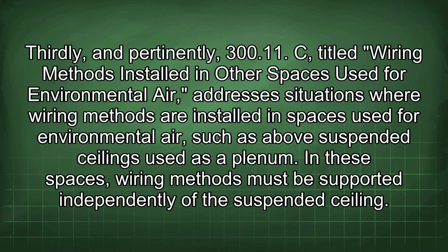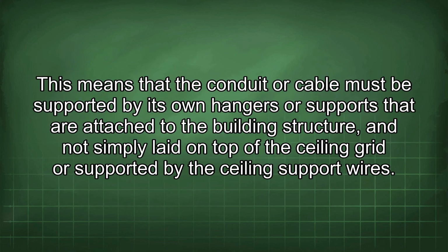Thirdly, and pertinently, 300.11 C, titled Wiring Methods Installed in Other Spaces Used for Environmental Air, addresses situations where wiring methods are installed in spaces used for environmental air, such as above suspended ceilings used as a plenum. In these spaces, wiring methods must be supported independently of the suspended ceiling. This means that the conduit or cable must be supported by its own hangers or supports that are attached to the building structure and not simply laid on top of the ceiling grid or supported by the ceiling support wires.